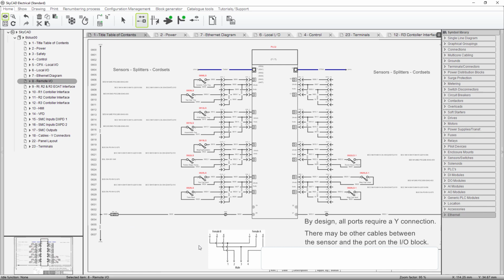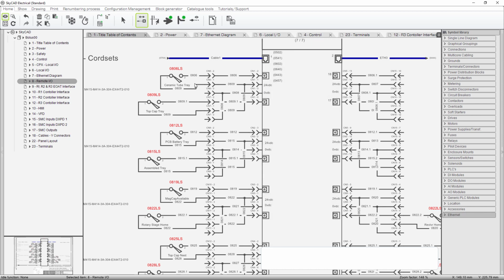And so if you look at the detail down here at the bottom, here's your 4 pins going into the armor block, and here's your 6 terminals, one from the one sensor and one from the other, because they share common and power. So if you look close here, I've got 24 volts going here and going here. This is 0 volts. And I don't show a conductor going over here, it's just implied. And you can do this with a field wireable connector, because this 4 is the 4 that has to screw in, plug into this block. But these 6 can actually be done with 4.